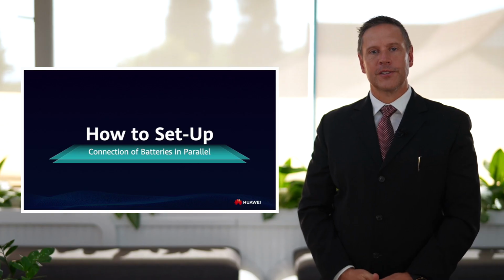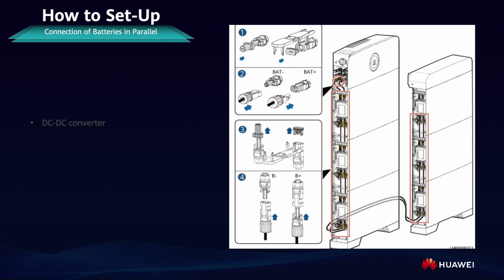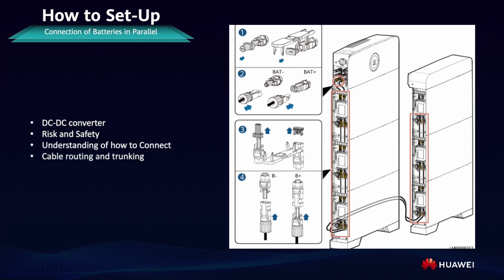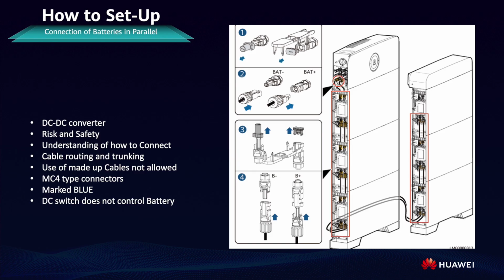Connections of batteries. Each battery does have a DC to DC converter. Therefore, pay attention to the risk and the safety. Understand how to connect. Make sure of the cable routing and trunking. Use of made-up cables is not allowed. MC4 type connectors must be used, that is marked blue. The DC switch does not control the battery.